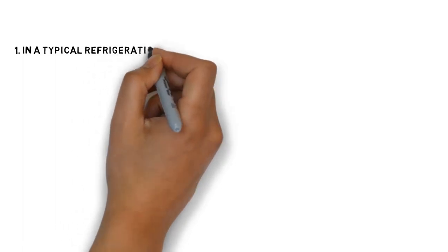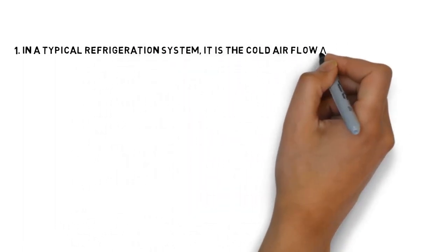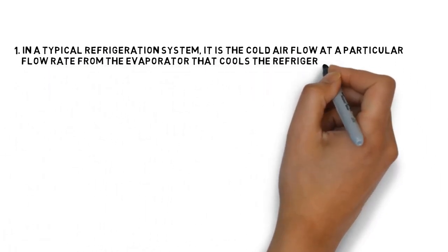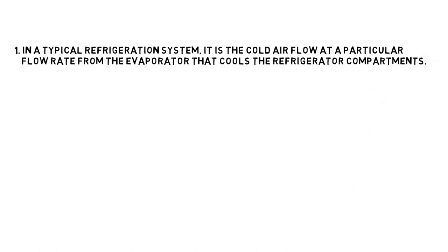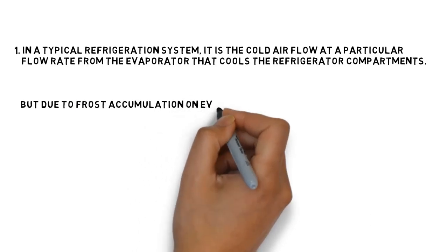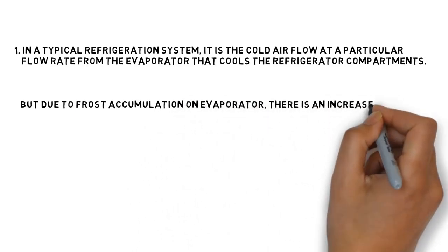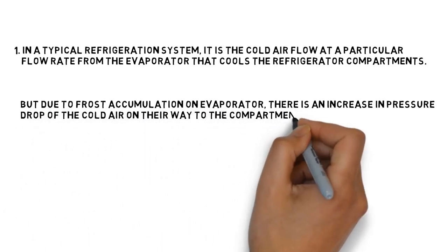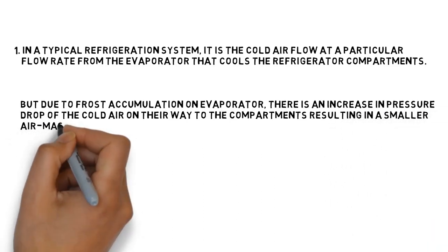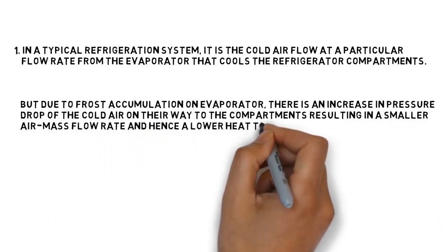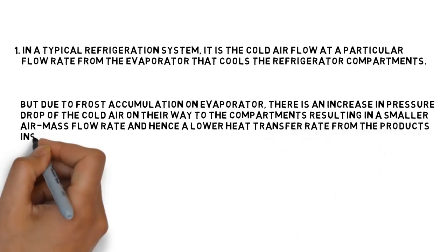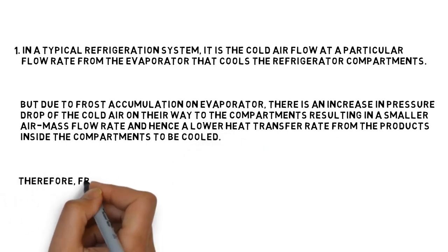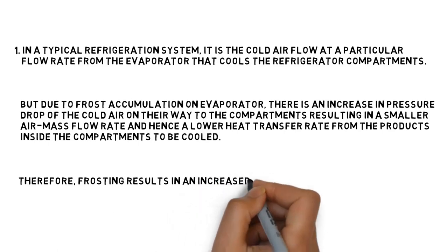In a typical refrigeration system, it is the cold air flow at a particular flow rate from the evaporator that cools the refrigerator compartments. But due to frost accumulation on evaporator, there is an increase in pressure drop of the cold air on their way to the compartments, resulting in a smaller air mass flow rate and hence a lower heat transfer rate from the products inside the compartments to be cooled. Therefore, frosting results in an increased energy input to accomplish the same refrigeration effect.